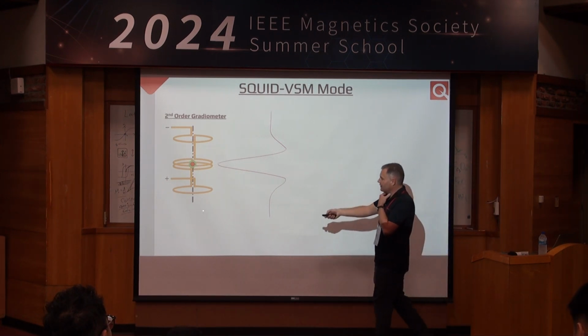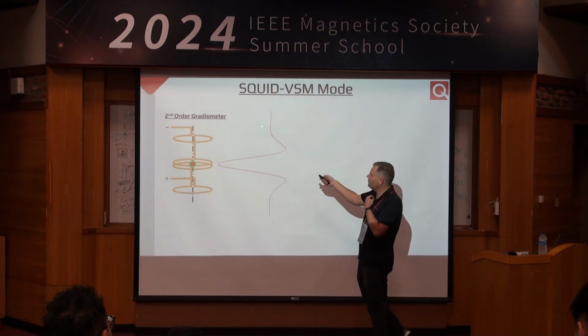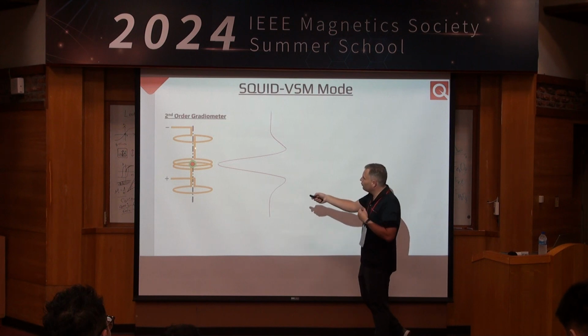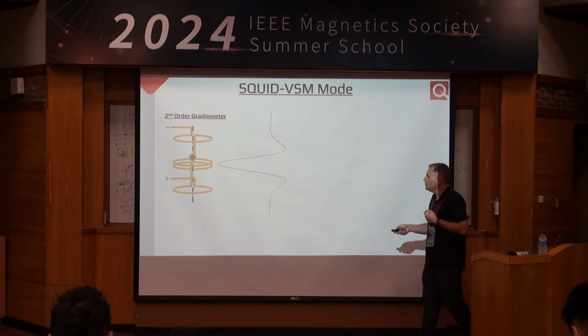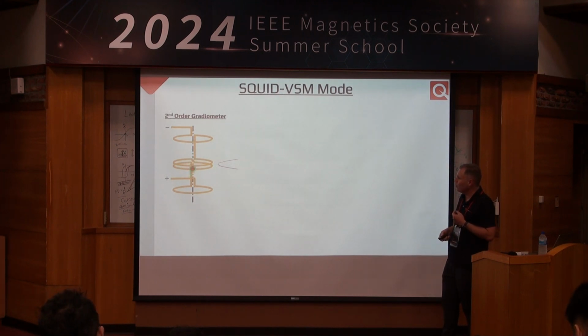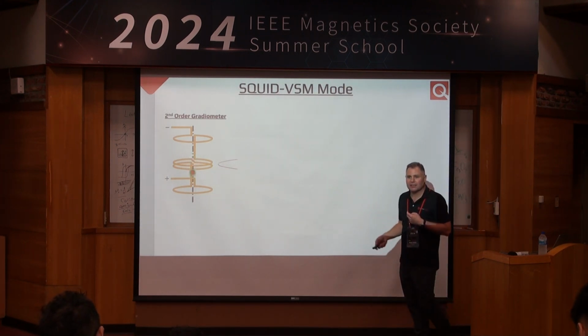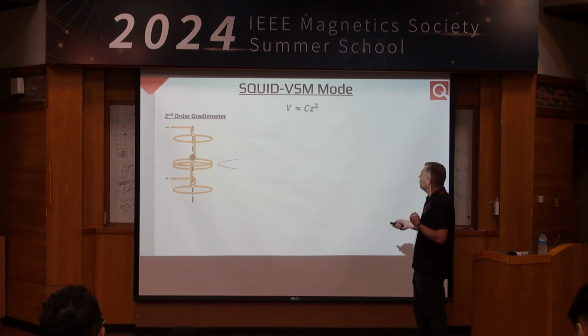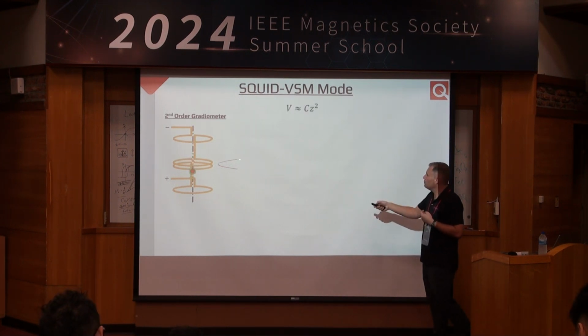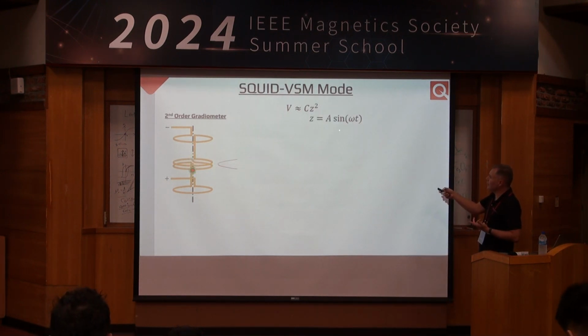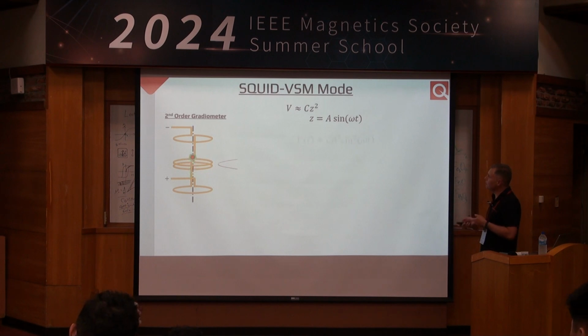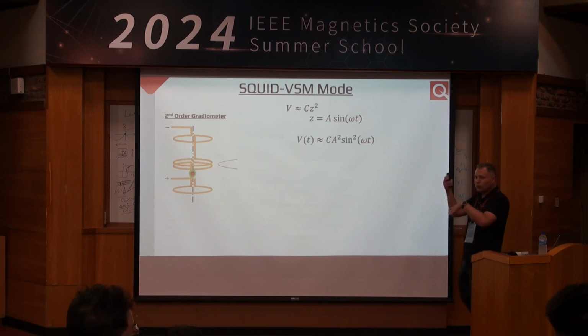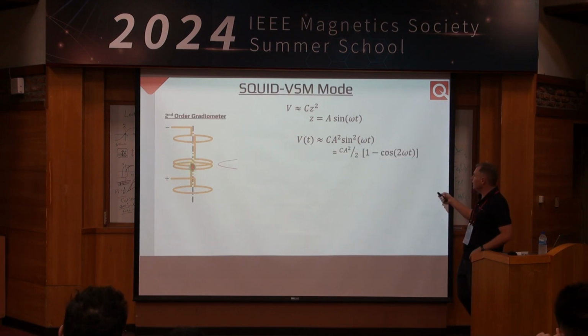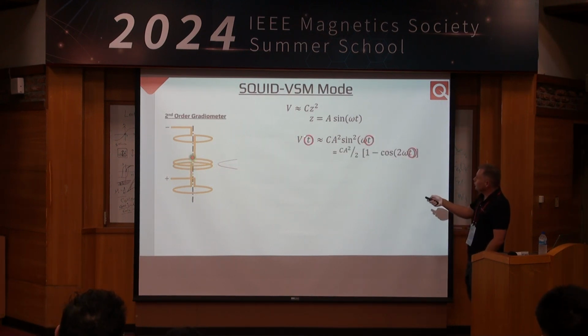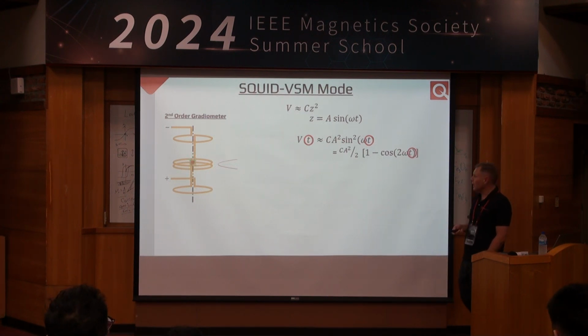So it's the same detection circuit, same second-order gradiometer, same voltage waveform. Here's our sample. But instead of moving the sample through the gradiometer, we're just going to jiggle it. Okay? So we don't have to worry about most of this waveform. We can throw that away. And all we have to deal with is this little parabolic section right here. Follow the bouncing ball. So again, we've got a parabolic voltage response here. We know the position of the sample as a function of time and frequency and with a given amplitude. Go through here, plug this in, use one of those trigonometric identities in the cover of the book, and we can get this type of voltage here. So this is interesting. We're now measuring the voltage not as a function of space, but as a function of time. And we're using a lock-in amplifier to do this.